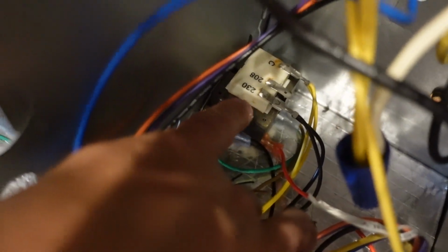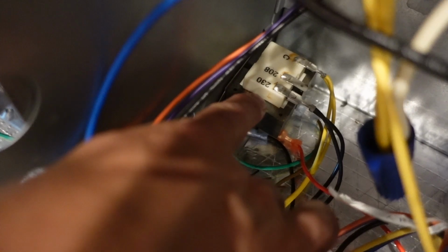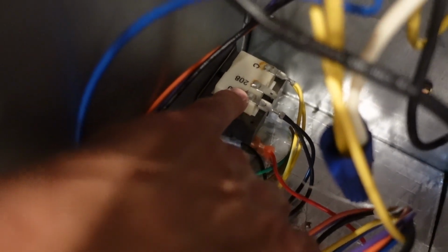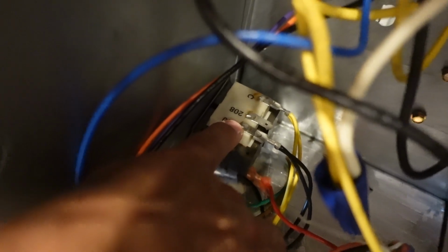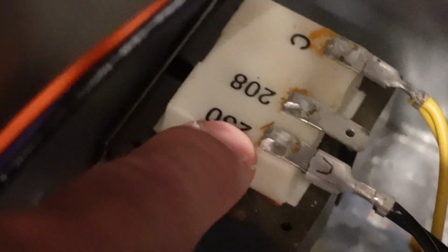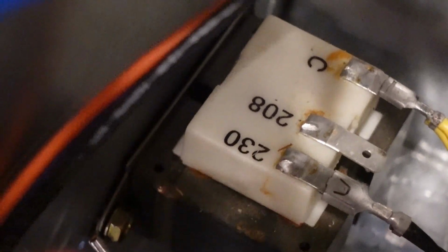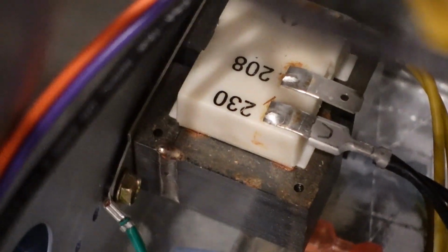Okay, so what we're looking at here is the heart of the low voltage control system that produces 24 volts. Incoming voltage on this unit is 230 volts. That can be a range of voltage. It could be 115, but in this case it's 230 because this is an air handler. Then we have 24 volts coming out right here. So I would call this my R terminal or hot terminal, and then my common comes off the bottom. As a technician, this can be very challenging to check just because it's difficult to get up in there, but you have to get up in there to actually check it at times.